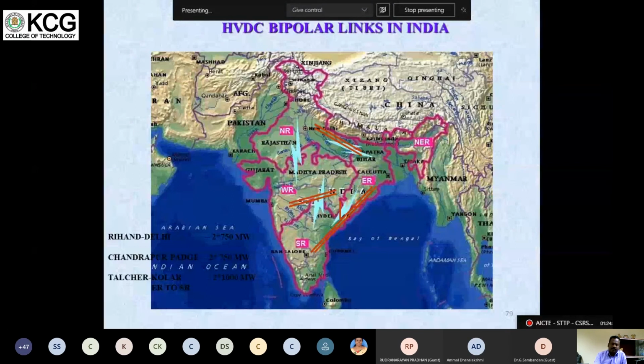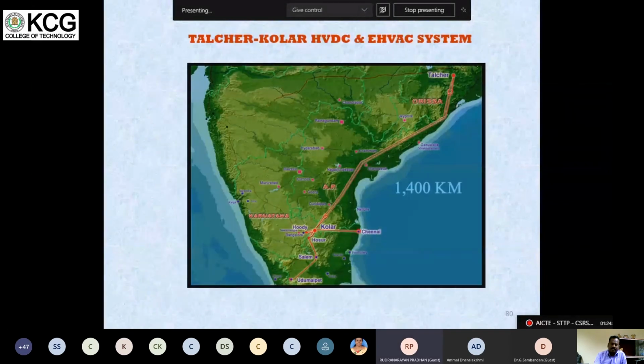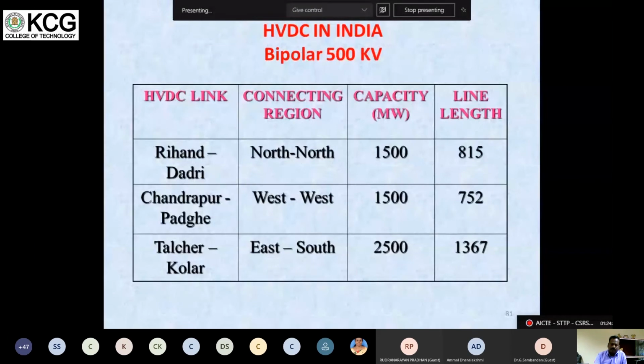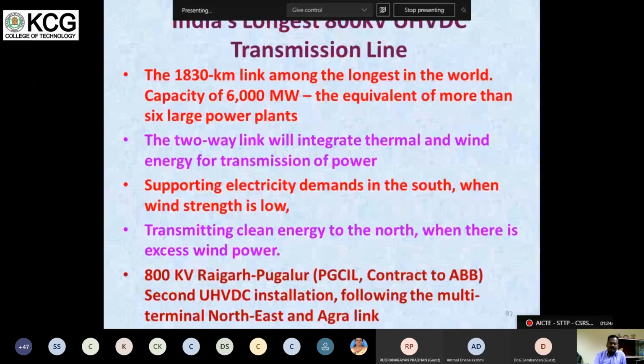These are a few HVDC bipolar links. This link is available in the southern region, from Talcher to Kolar. Talcher to Kolar is 2,500 megawatt. The line length, as you can see, is 1,367 kilometers, a long distance line. If it were AC, huge losses might occur, but since it is a DC system, losses are very less. It connects the eastern region to the southern region. It started with 2,000 megawatt and was enhanced to 2,500 megawatt with the use of a 500 kV system.